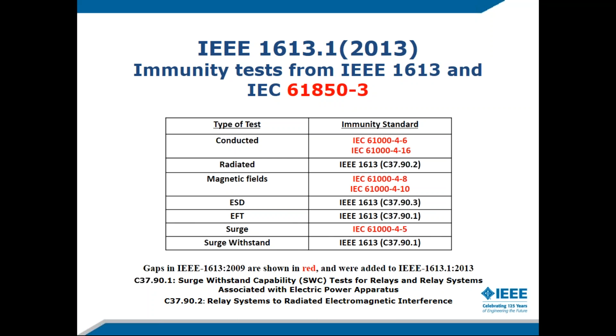But it's useful to know that at that point in the standard, they're worried about radiated immunity, electrostatic discharge, electric fast transient, and surge withstand. They didn't get into surge or lightning, and that was picked up with the IEC, showing that they want to test to 4-5. And the C37.90 standards have been used for testing relay systems for quite some time, probably decades. And so some of the testing I show up there in parentheses show up in C37.90.1 and .2, and I showed that they were picked up in 1613.